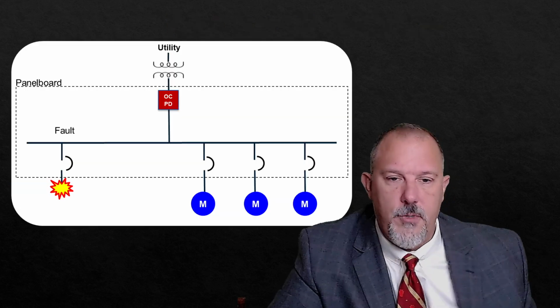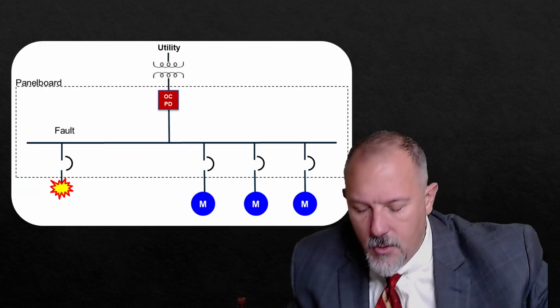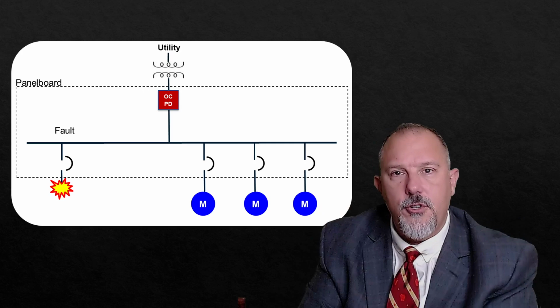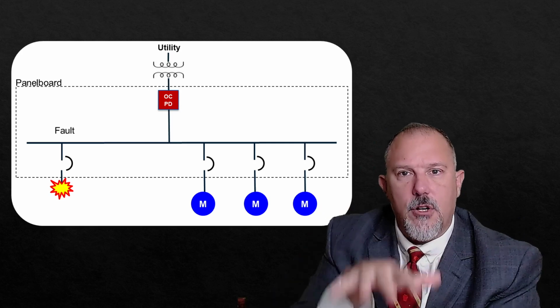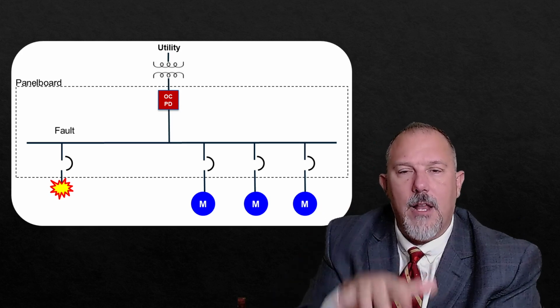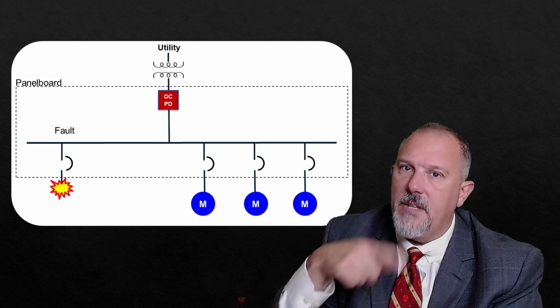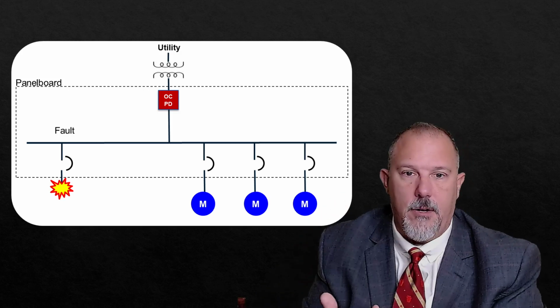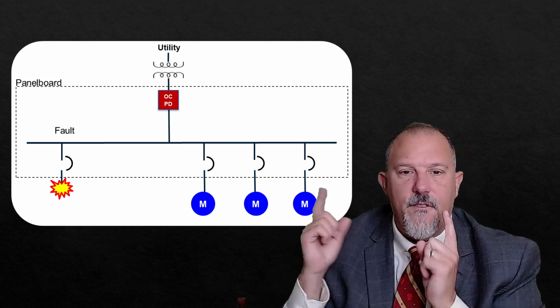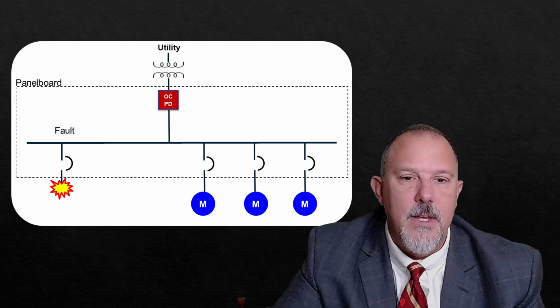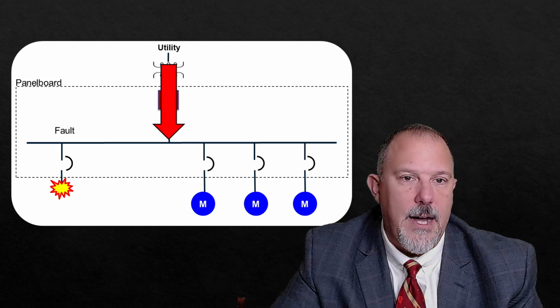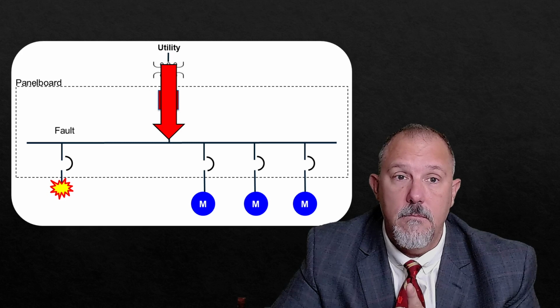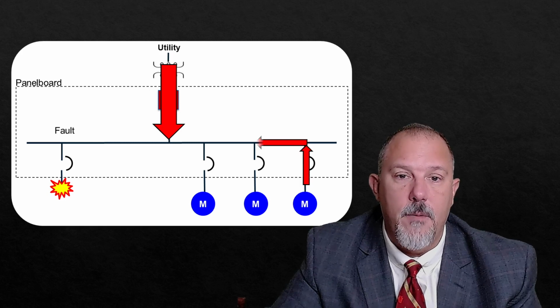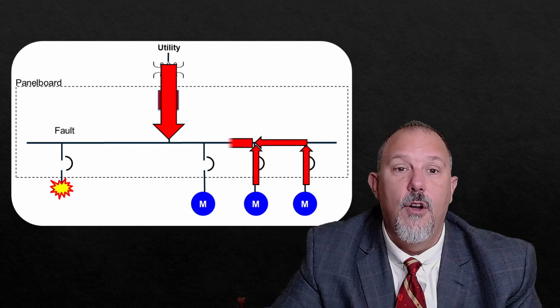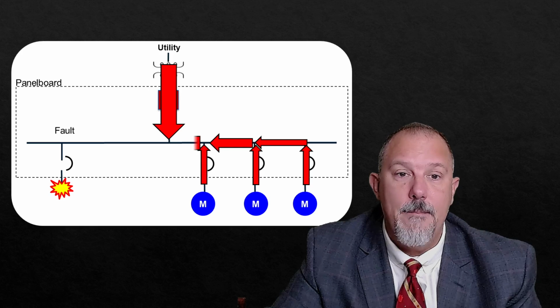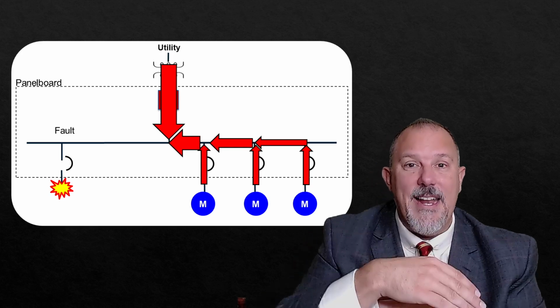Now, I mentioned motor contribution. What is motor contribution? If you think about a motor, when you have a short circuit in your system, you're going to collapse the voltage across the windings. When you collapse the voltage, the rotor is still going to be spinning. It becomes a generator. So when I have a fault, like I show in this system, I have fault current coming from the utility, and from each of these motors. And all of those will add up.